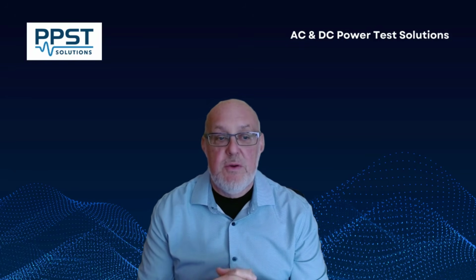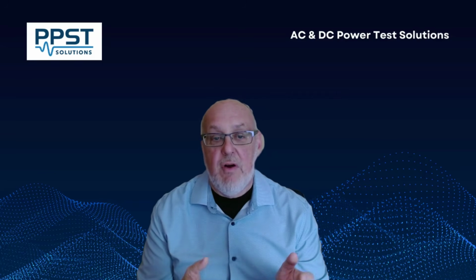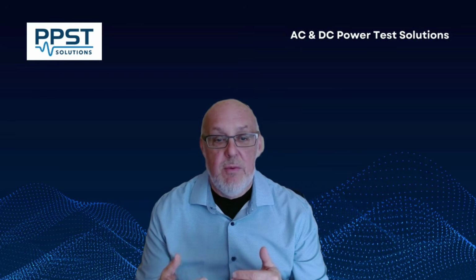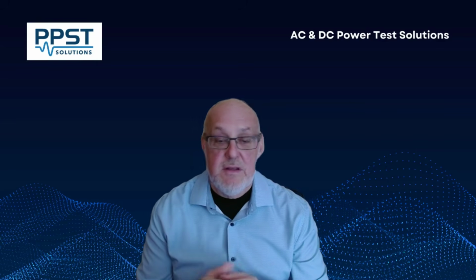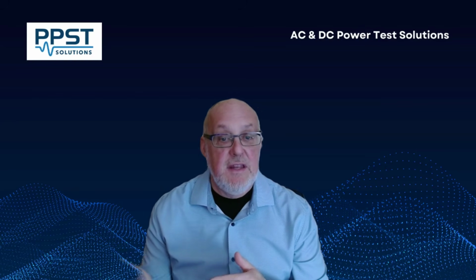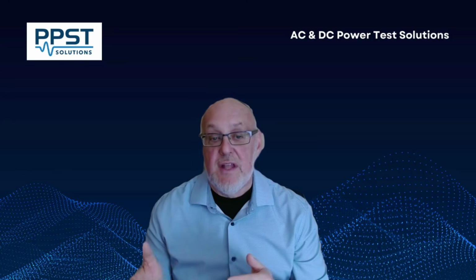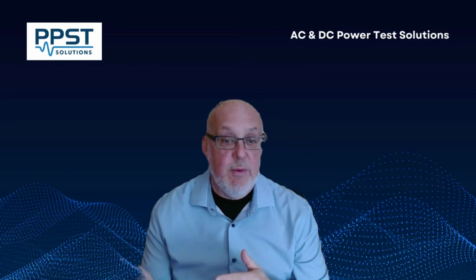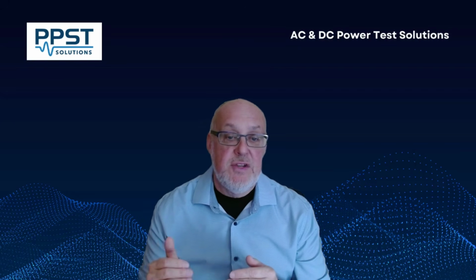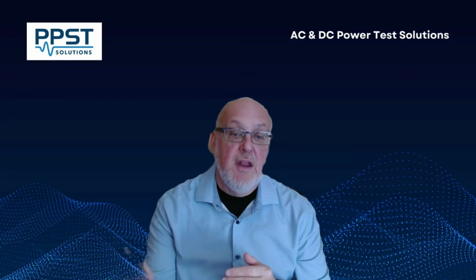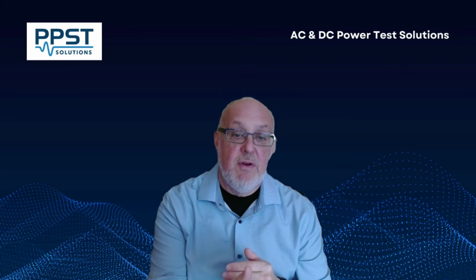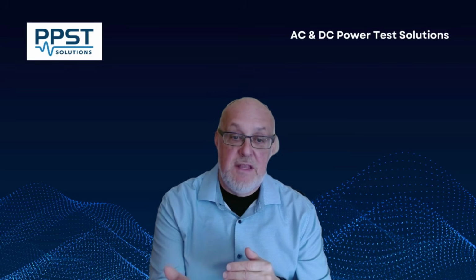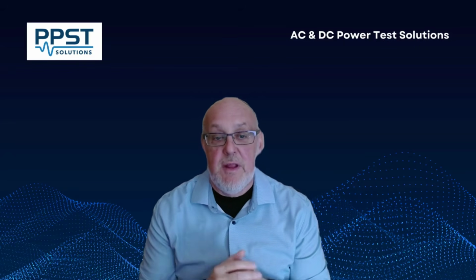So what we would do is we would have a megawatt of our energy going through. If we were to feed that to a unit under test, maybe a UPS, or it could be an AC to DC converter, or a solid state transformer, or a transformer. Ideally, that energy would go through that device, and it could go through another regenerative product that could either be DC to AC or AC to AC, feeding that back into the utility.